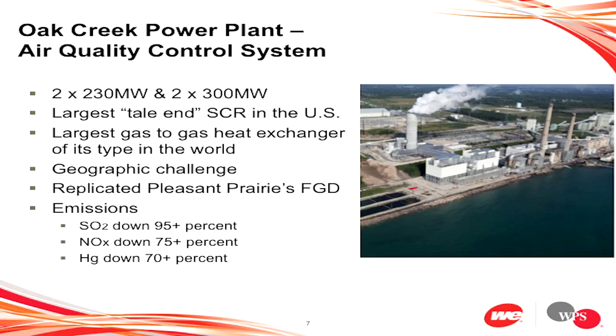So we ducted the flue gas from the 4 boilers to the south, and ended up installing the largest tail-end SCR in the US, and the largest gas-to-gas heat exchanger of its type in the world. Again, very significant environmental benefits: 95% reduction in SO2, 75% reduction in NOx, and mercury down more than 70%.